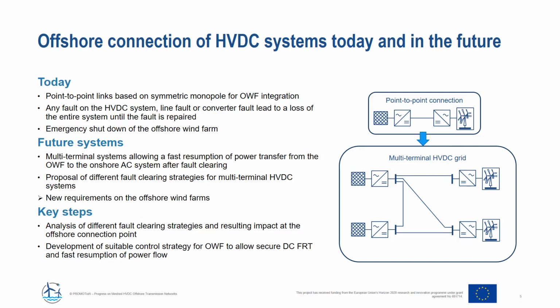Within this presentation, we're going to first do an analysis of different fault clearing strategies and the resulting impact at the offshore connection point, and then go into more detail on the development of a suitable control strategy for the offshore wind farm to allow a secure DC fault ride-through and fast resumption of power flow.